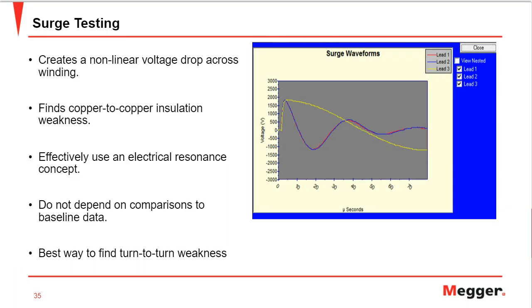Just to start with the surge test and give some background, let's take an example of this surge waveform. What we are trying to see is that all three waveforms should superimpose on each other, with a difference of less than a 10% threshold when comparing all three waveforms. Here, it's definitely not the case on the screen. The lead 3, the yellow line, is clearly out of sync with the other two waveforms, which gives an indication of a turn fault or other faults as well.